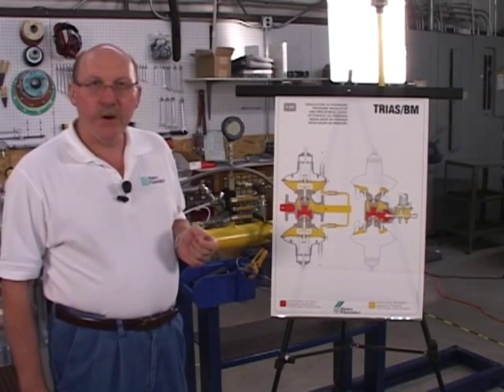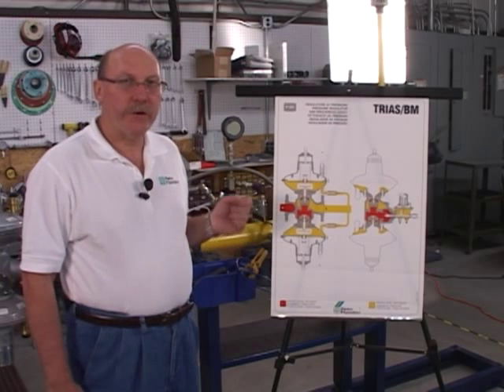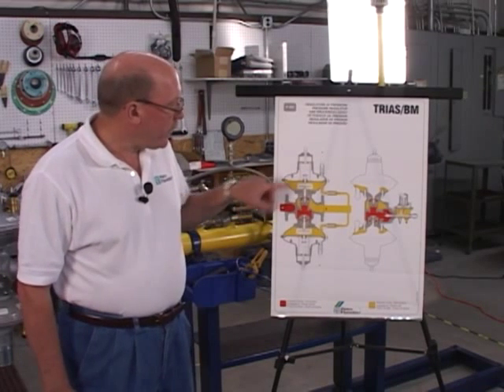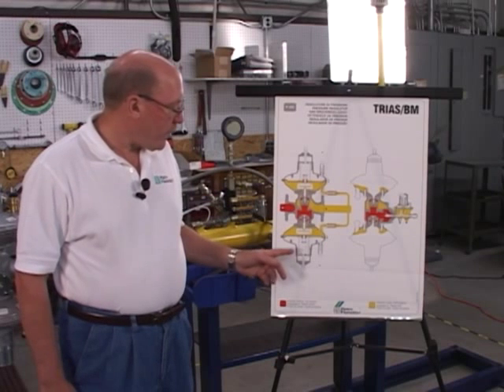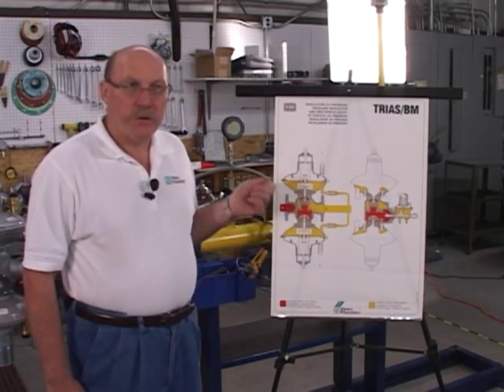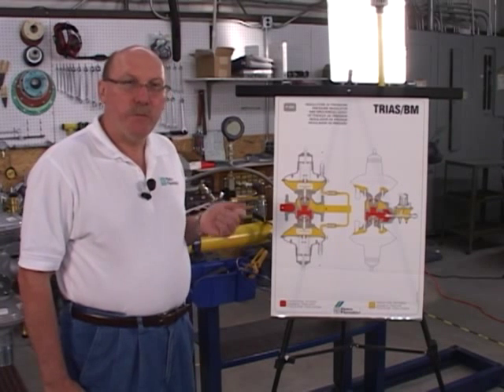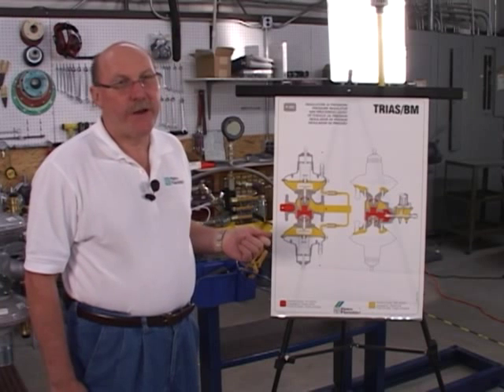The TRIAS regulator is an unusual regulator because rather than having a worker and a monitor regulator separately in the line, we use a worker regulator on top and a monitor regulator on the bottom in one body. The TRIAS is a spring operated regulator but gives you pilot operated outlet pressure accuracy.